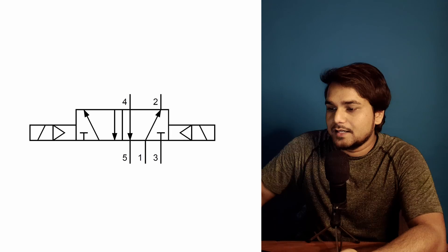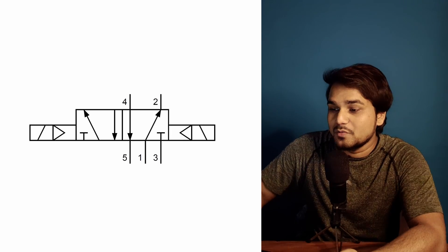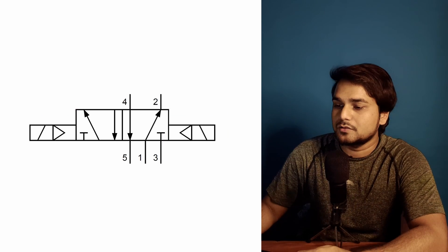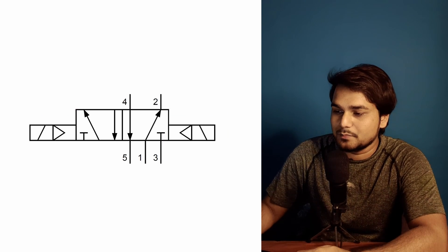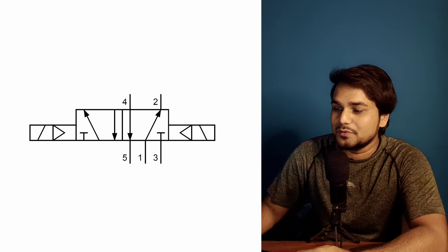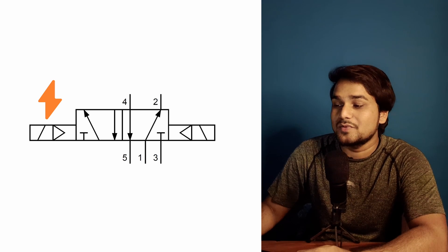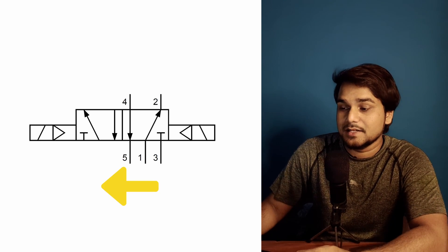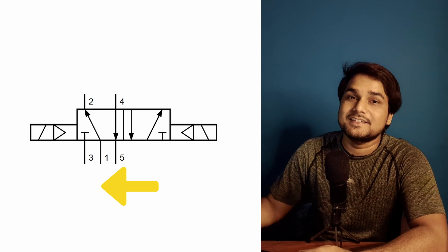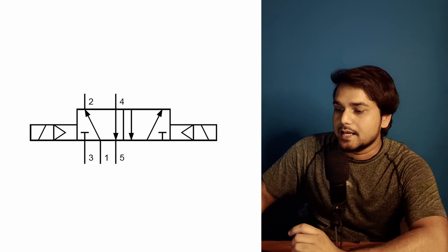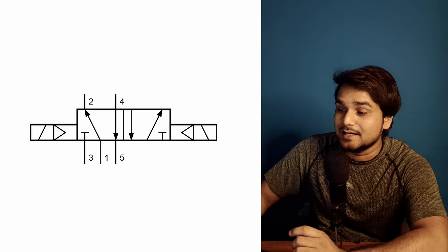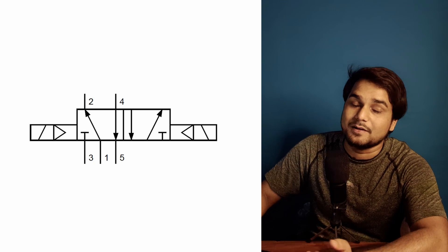5/2 solenoid valves come in double coil and single coil with spring return. In a 5/2 double solenoid valve there are two solenoids, one at each end. To switch the position state, you give a signal once to one solenoid and the valve spool will shift to that side and remain there until a signal is given to the other solenoid.